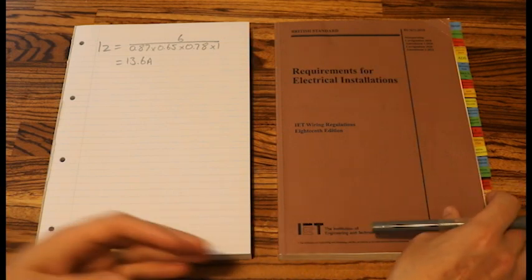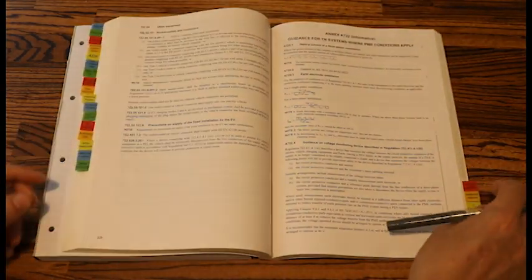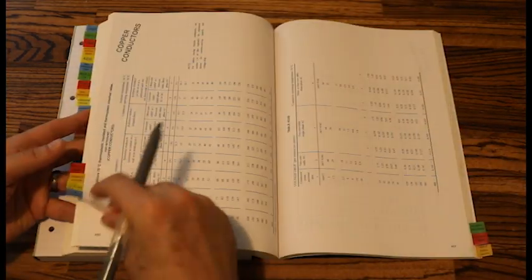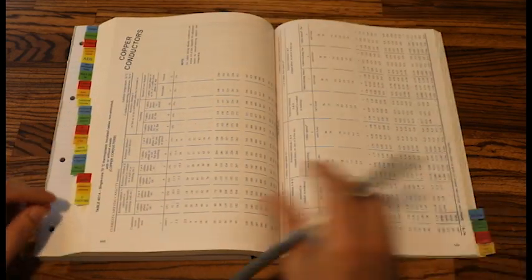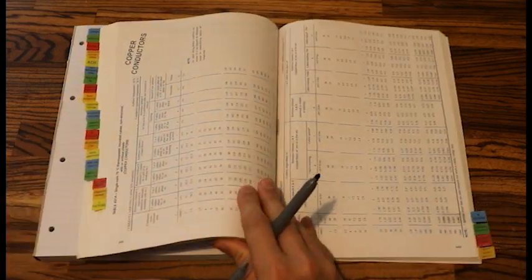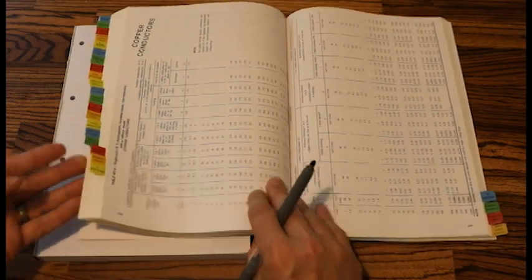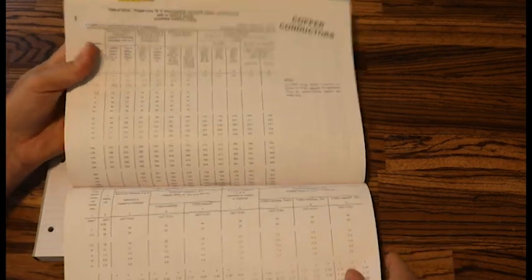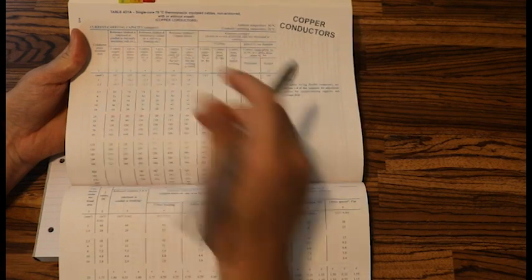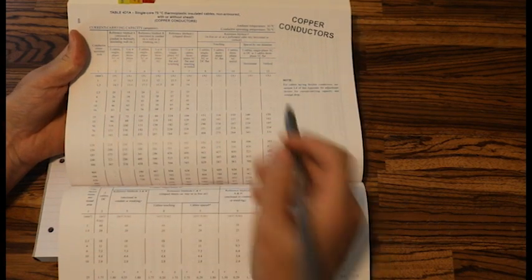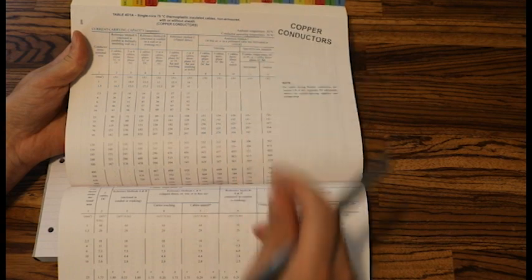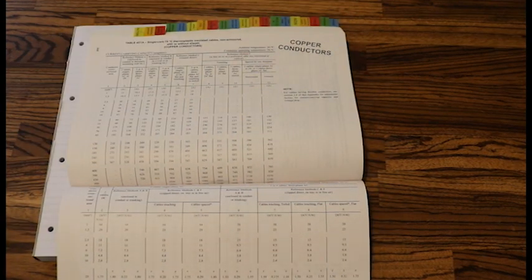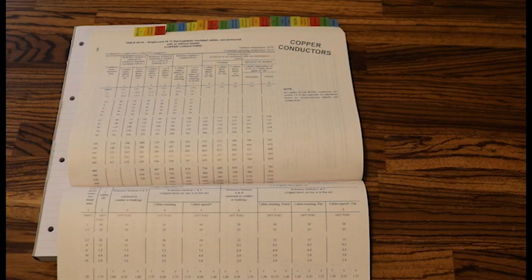So if we look at the IET tables right towards the back, take our IET tab, and they start on page 448. So it's important we choose the right table. We've got to know which table to look at. So the first one as you can see it says single core 70 degree thermoplastic insulated non-armoured. This is singles non-armoured. Our question stated that we are using singles non-armoured, so this is our correct table.